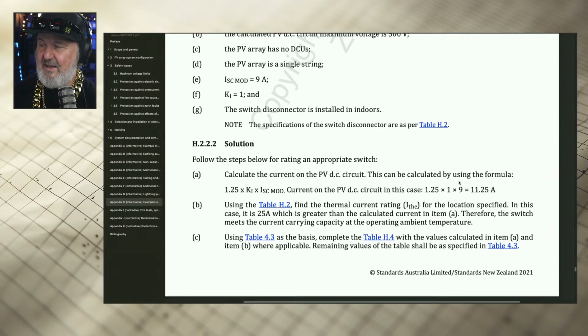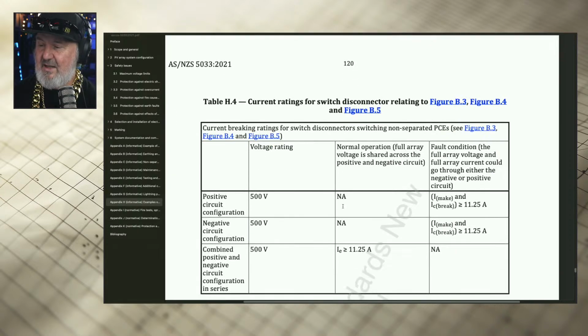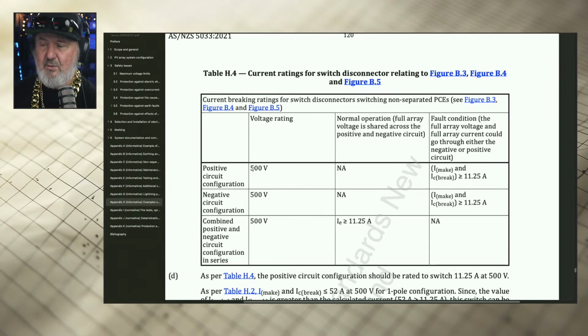So we come down here, and because this is only a 9 amp ISC, these panels have a lower current than the previous example. We have 11.25 amps of potential fault current, allowing for high irradiance, and now we have to find a switch that can interrupt 11.25 amps, but now it's on only the positive leg or the negative leg, so 2 poles in series in this example, not 4 poles in series. So we go down here and we see that on the positive leg we could have up to 500 volts with an earth fault, and on the negative leg up to 500 volts with an earth fault, and the combined really doesn't apply under an earth fault anyway, because it's going to pass through the inverter through to the MEN, so it's not actually passing through both poles.